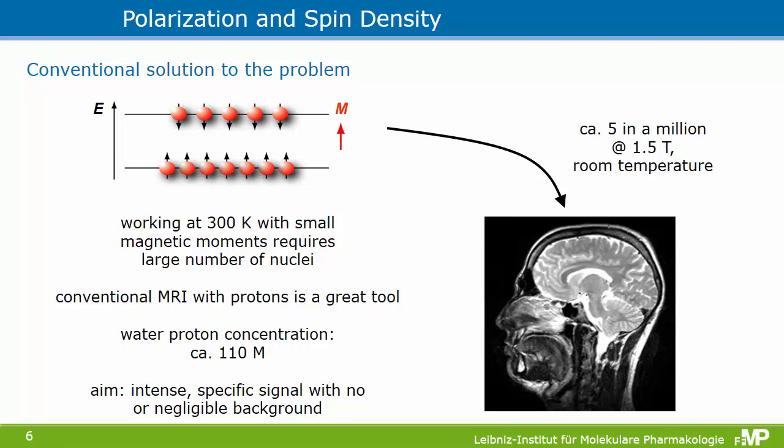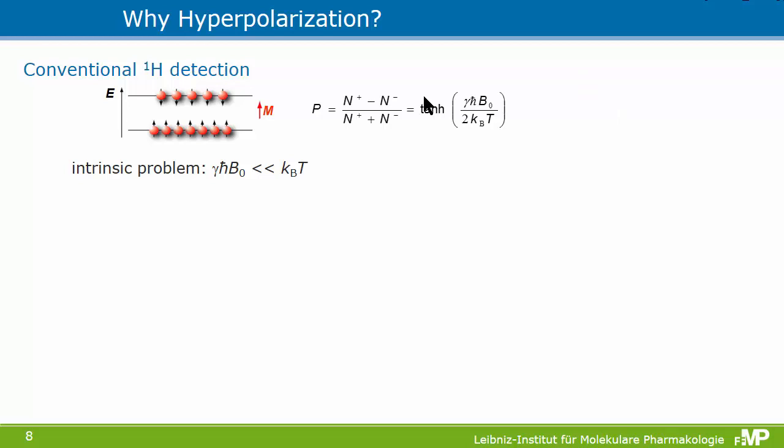The aim of hyperpolarization techniques is to go from a condition with very small overpopulation to a condition with an artificially increased overpopulation, giving a tremendous enhancement in the magnetization so that we can detect things at much lower concentrations. As a rule of thumb, at an external field of 1.5 Tesla only five in a million spins contribute at room temperature to the signal. Conventional imaging works because we have a large spin pool, but hyperpolarization aims for an intense specific signal with no or negligible background.